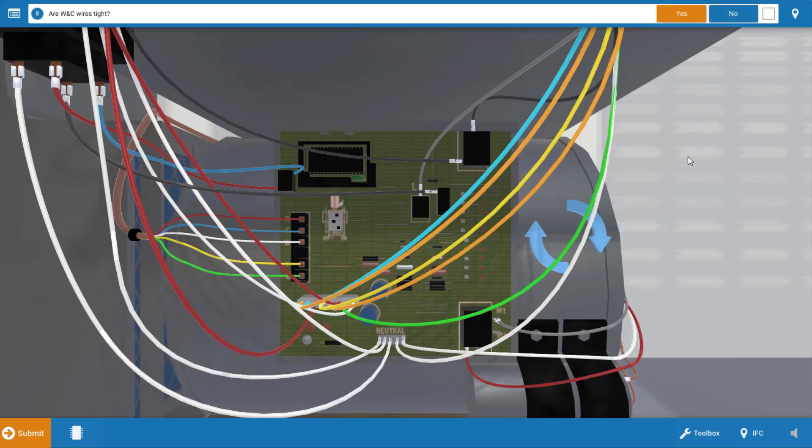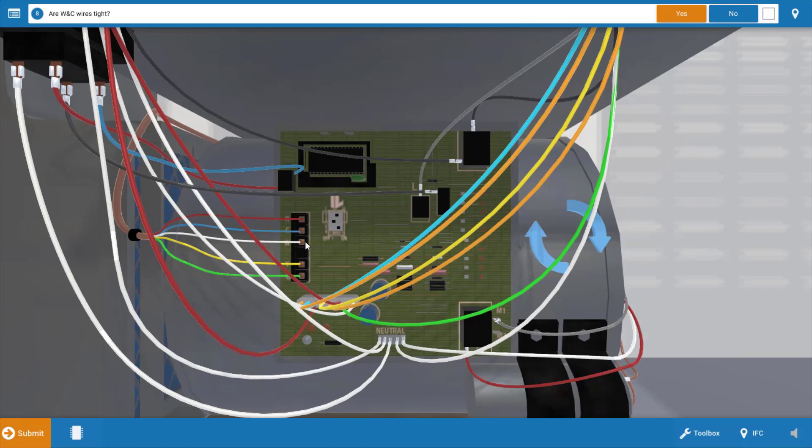Now this pretty much verifies that the thermostat is most likely our culprit, but we want to check the wiring connections down here at the IFC to make sure they're secure, and they do appear to be secure so that the wires are tight with no loose connections.